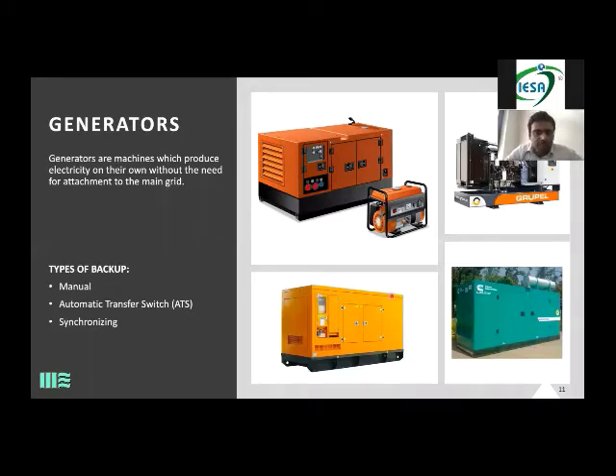The types of backups which are available are basically: one is manual, the second is the automatic transfer switch, and third is synchronization, which I think are normally being used as of now. Just to give you a brief, what is a manual changeover? If you have one genset running and a hot backup, if something happens, the load gets transferred from one genset to another via a manual changeover. The person has to be present on site to shift the power from one genset to another. That could be time consuming, because from the time you realize something has happened on site and pass on the message on a walkie or by a phone call, you can lose 15 seconds to maybe 1, 2, 3 minutes before the load goes from one genset to the other.